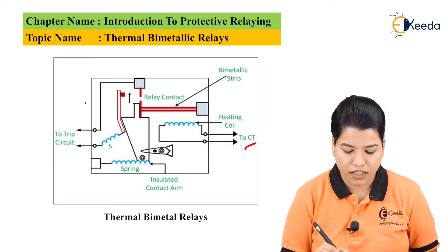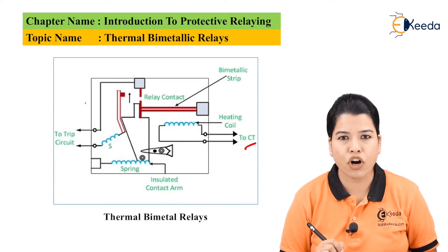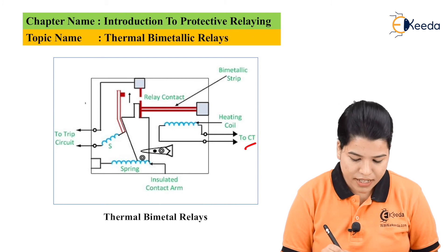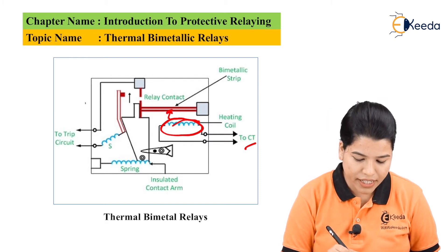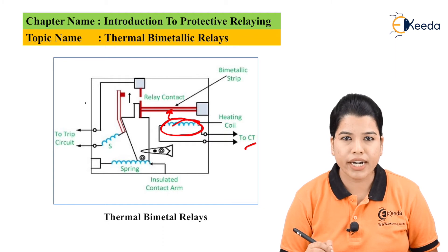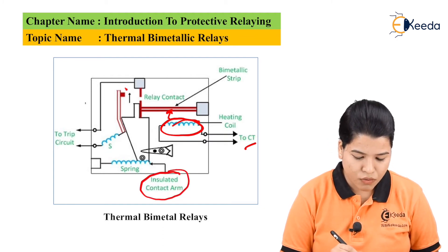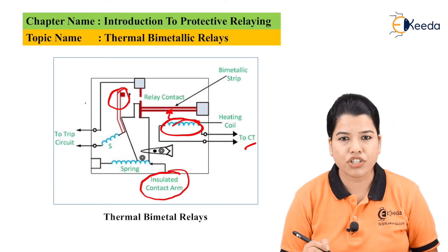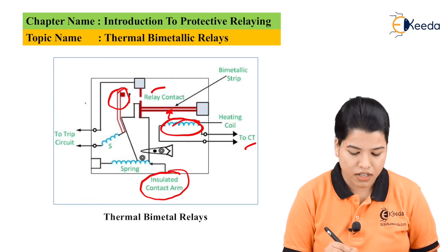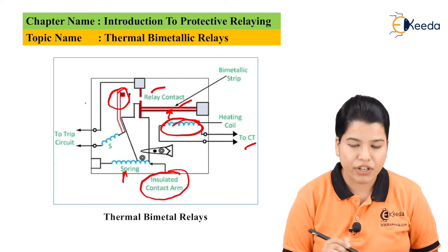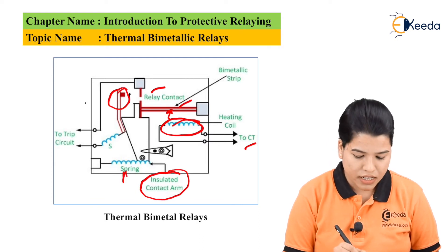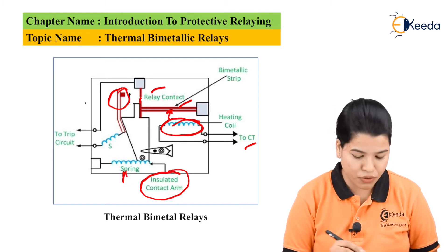Under normal operating conditions, the current sensed by the CT is normal, so no significant heat is produced. When a fault occurs, heavy current causes heat to increase, and this temperature is sensed by the heating coil, which then heats the bimetallic strip. Under normal conditions, the insulated contact arm is held far away from the relay contacts, but when a fault occurs, the heat generated causes bending of the bimetallic strip, releasing the spring's pressure and closing the trip contact of the relay.